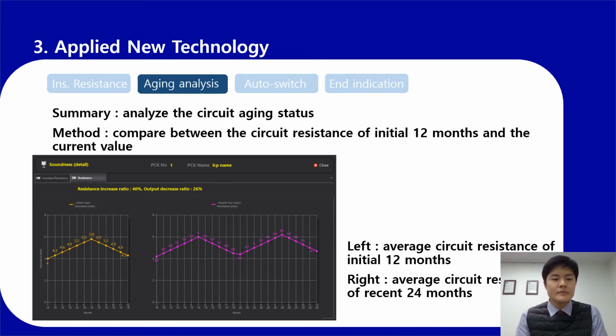Self-regulating heating cable has the character of changing the molecular structure according to the temperature environment. In the winter season, its structure shrinks to reduce the resistance to increase the output. In the summer season, its structure expands to increase the resistance to reduce the output. As the molecular structure expands and shrinks, the circuit goes through an aging process as it becomes aged. Even in the winter season, the molecular structure does not shrink enough. Thus, the resistance increases and output decreases.